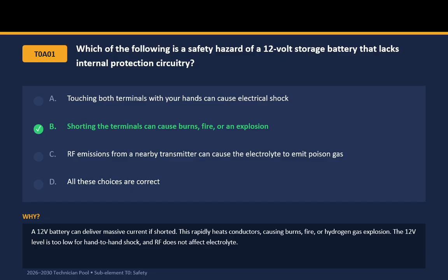Which of the following is a safety hazard of a 12-volt storage battery that lacks internal protection circuitry? B. Shorting the terminals can cause burns, fire, or an explosion. A 12-volt battery can deliver massive current if shorted. This rapidly heats conductors, causing burns, fire, or hydrogen gas explosions. The 12-volt level is too low for hand-to-hand shock, and RF does not affect electrolyte.